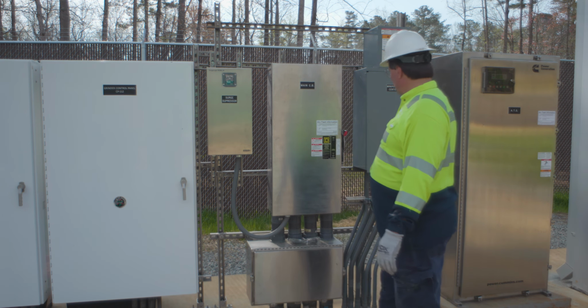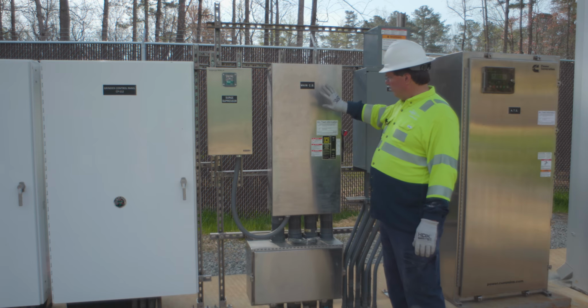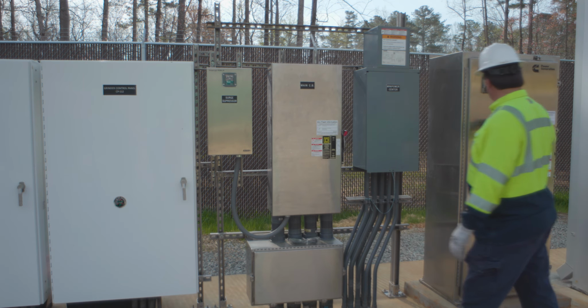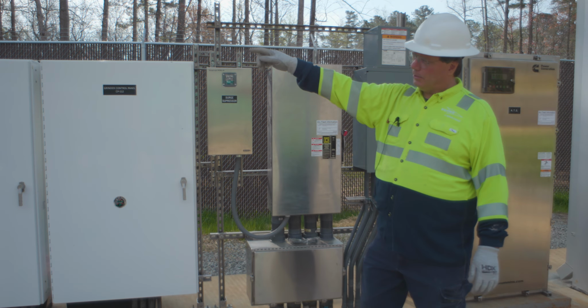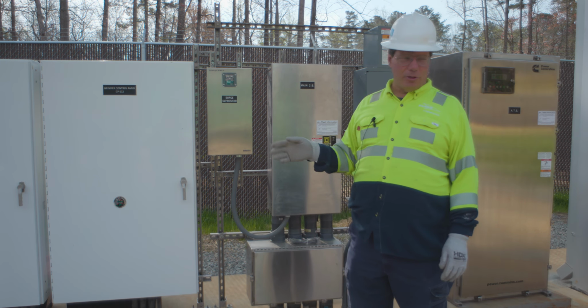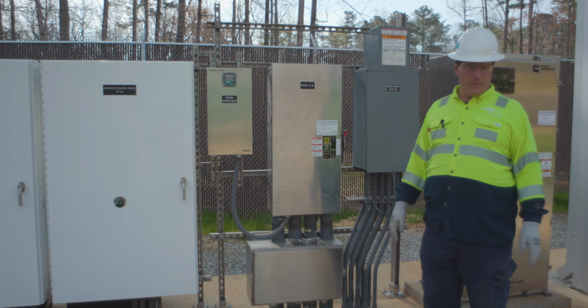And like I was talking about earlier, the main circuit breaker goes to the transfer switch. From the transfer switch, everything goes to the control panels, and then from the control panels it goes out to all the different devices. The reason it goes to the transfer switch first is because if there's a power loss, then the transfer switch will connect to the generator and that way everything is still connected to power as it switches from one to the other. If we came straight off the breaker, then when the transfer switch switched, nothing would be connected to the generator. So we connect to the transfer switch first, and then the generator is connected to the other side of the transfer switch, and then the load is connected and it switches between the main circuit breaker and the generator.